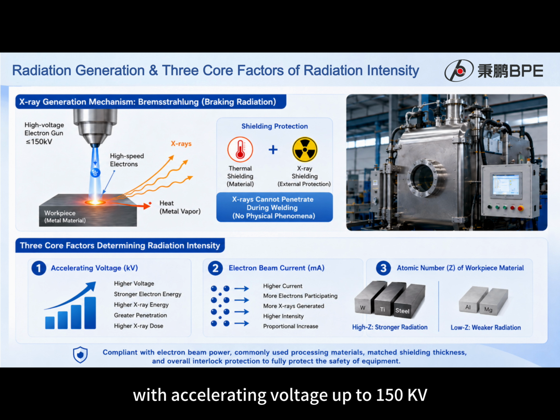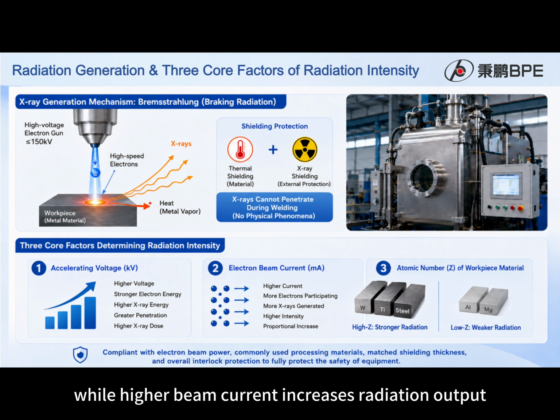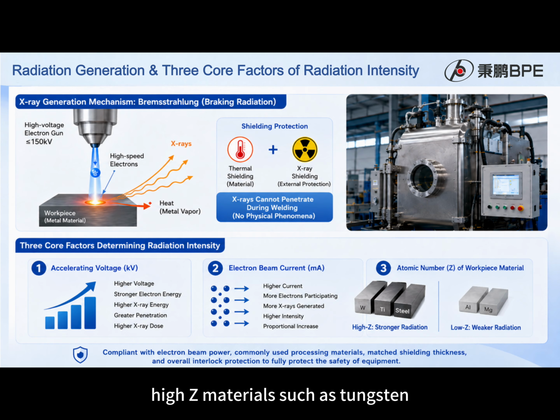Radiation dose rate and penetration are mainly determined by three factors: accelerating voltage, beam current, and material atomic number. Higher accelerating voltage produces more penetrating X-rays, while higher beam current increases radiation output. High-Z materials such as tungsten, titanium, and stainless steel generate stronger radiation, whereas aluminum and magnesium alloys produce significantly lower levels. Bingpeng designs shielding thickness according to electron gun power and the materials being processed, covering worst-case welding conditions.